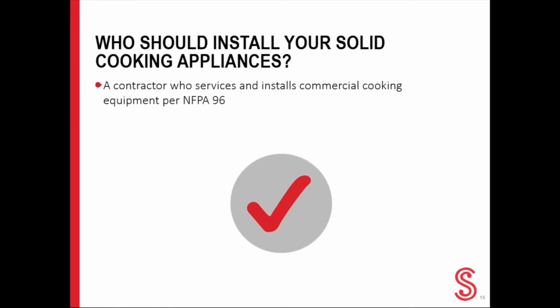So who should install your solid fuel cooking appliances? What you may be thinking right now: the installation standards are complex and very important, so you should never try to install a solid fuel cooking appliance on your own. You want to select a contractor who services and installs commercial cooking equipment per NFPA 96 codes. They know the standard and will make sure the installation meets the standards. So where can you find these contractors?